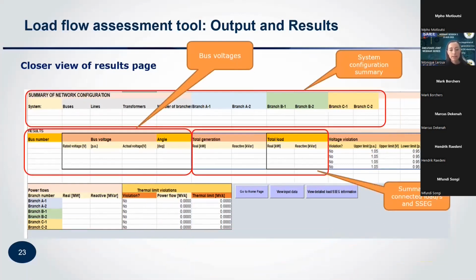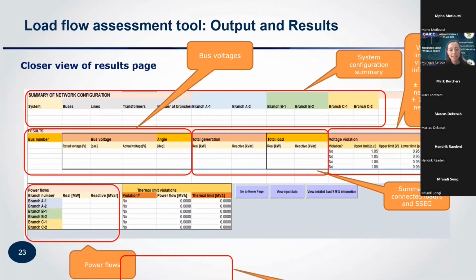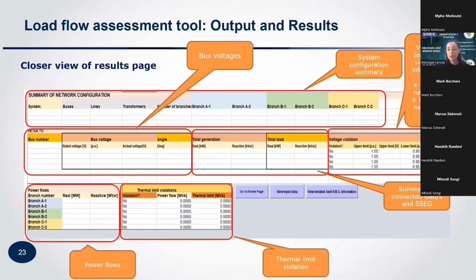Sorry, I should have done this. Okay, your voltage limitation, obviously for MV networks, it will look at where it's above or below the plus minus 5% threshold, and for LV networks, it will look at where it's above or below the plus minus 10% threshold, and those values will be captured in here, and the user can get it from there.